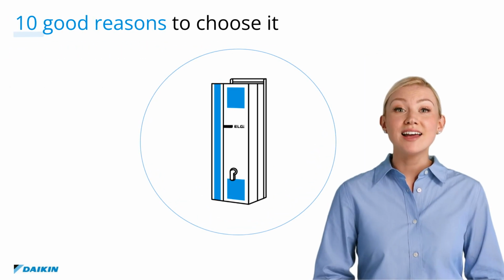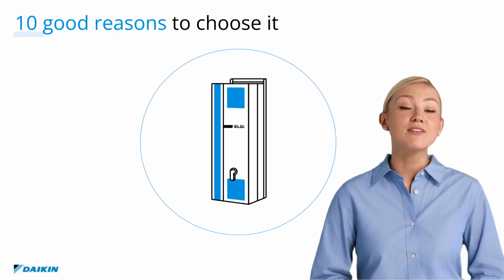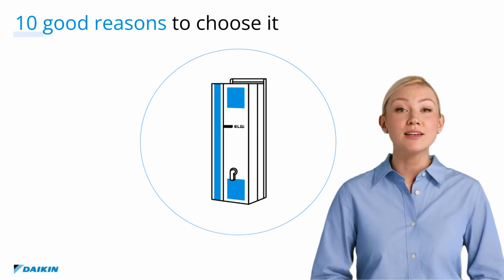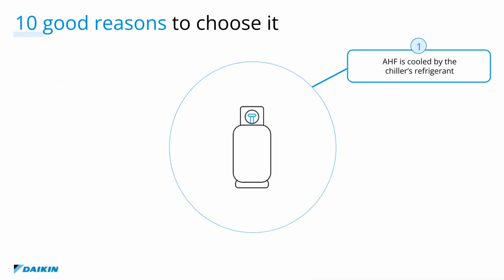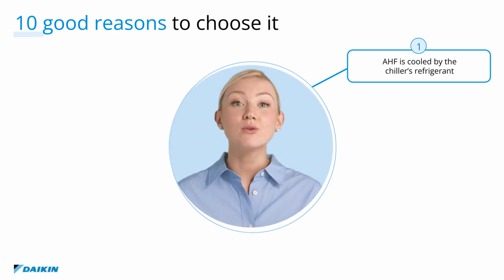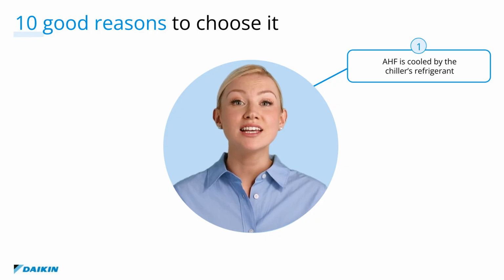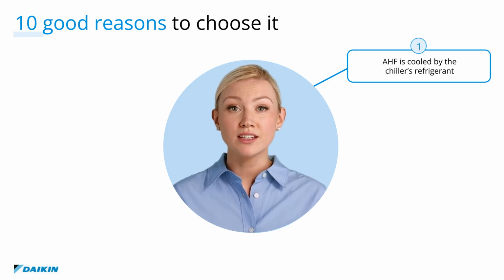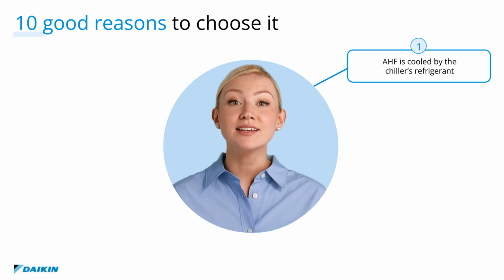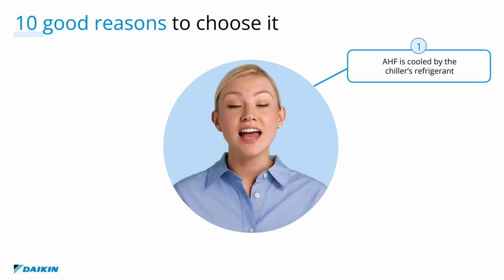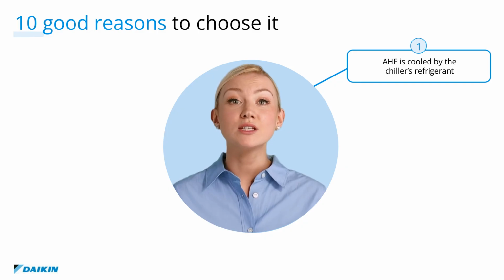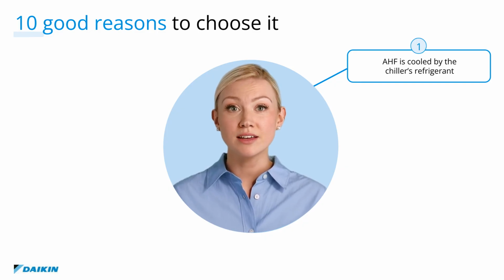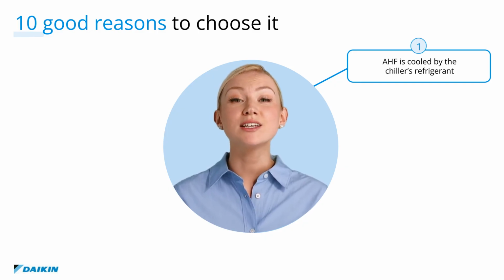Now, I will outline 10 reasons why choosing Daikin's Active Harmonic Filter is an effective way to meet these requirements. Let's start from the core. The Active Harmonic Filter is cooled directly by the chiller's refrigerant. Unlike air-cooled filters, which are prone to performance degradation in dusty or hot environments, refrigerant cooling ensures consistent thermal stability. That means no dependence on airflow, no dust accumulation, and no drop in cooling performance. It's a smart way to eliminate one more point of failure, particularly in high temperature or polluted technical rooms.